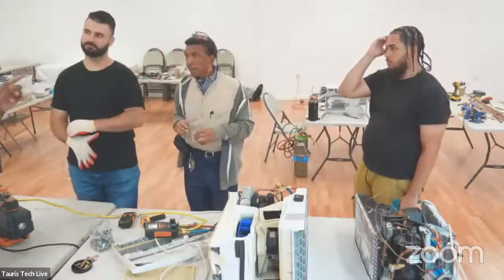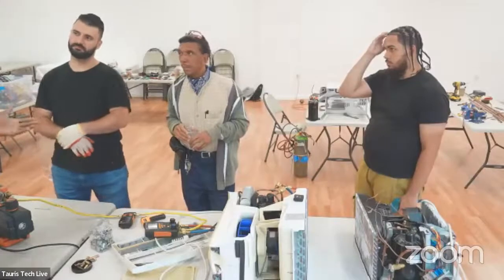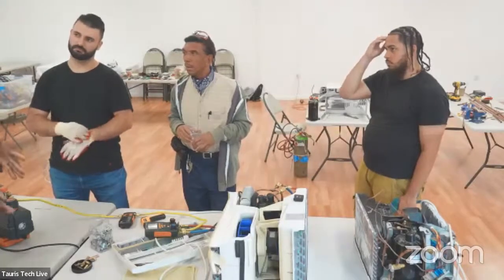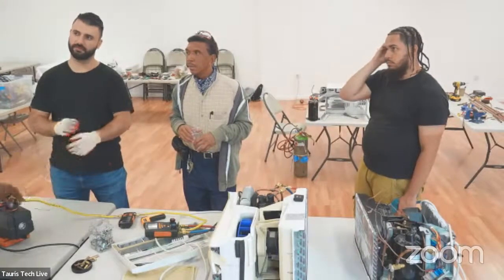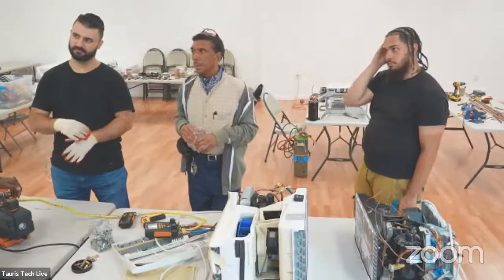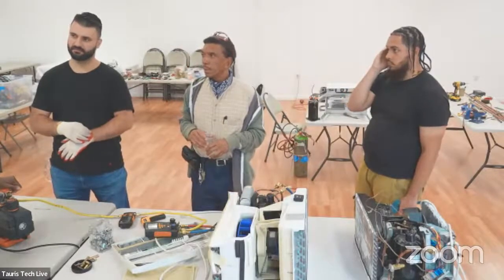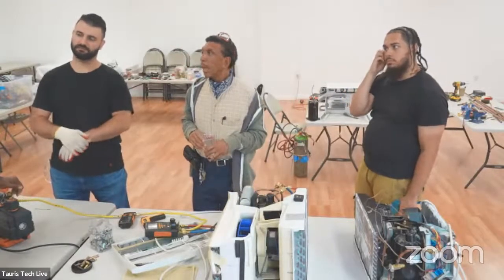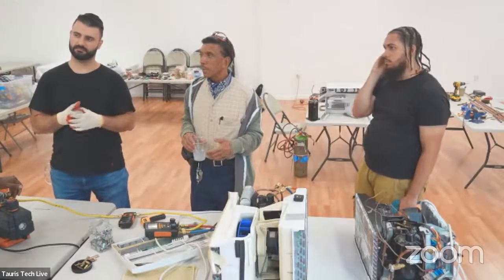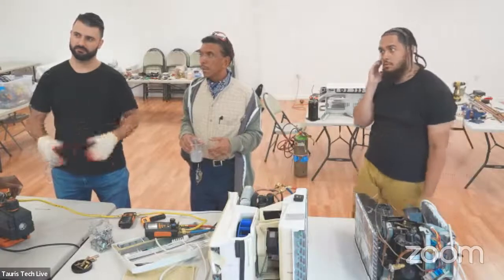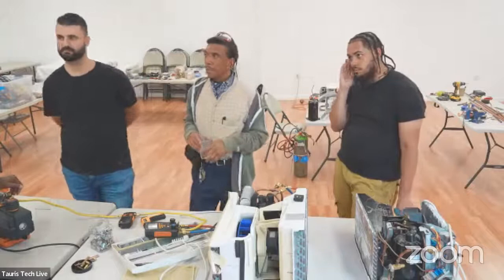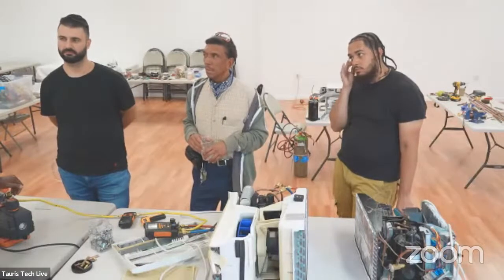So here's the question none of you guys asked me. Why would anybody use an absorption system instead of a regular chiller? Well, it doesn't require the license because there's no what? Refrigerant. No, water is the refrigerant. So Freon is just man-made refrigerant. Water is a refrigerant. Ammonia is a refrigerant. Anything that can be made to boil. Ice is a refrigerant. Carbon dioxide is a refrigerant. Anything is a refrigerant.